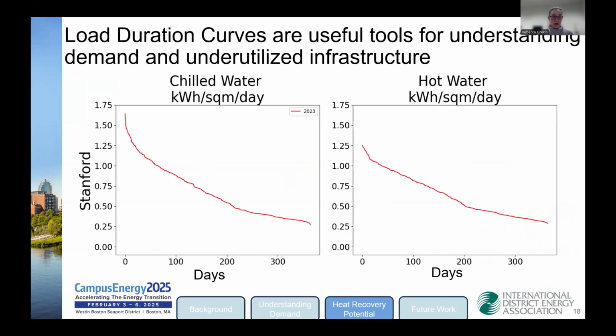So now another way to think about the impact that is associated with installing a heat recovery chiller is looking at a load duration curve. A load duration curve is another way to look at load data. Basically, you take the demand for a utility for the entire year, and you just sort it from largest demand to smallest demand. Here on the left is your largest demand for an entire year, in this case for Stanford in 2023, and on the right, you have the lowest demand that happened during that year. This does not necessarily represent January, and this does not necessarily represent December. They're just sorted by the demand for a single day.